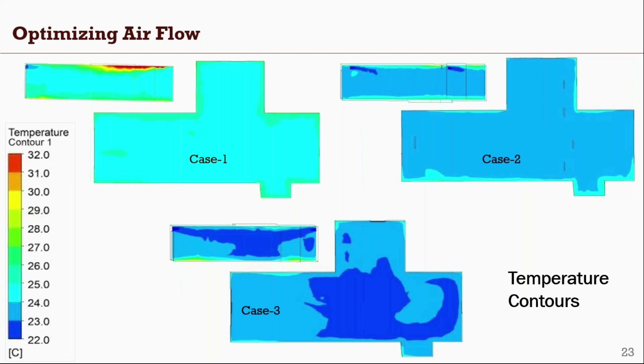This is the air velocity vector. In case 1, there are 4 diffusers from which velocity is flowing. In case 2, the diffuser location has been changed, and you can see the effect. In case 3, the diffuser location and number of diffusers have been changed. Case 3 has the lowest airflow speed at 1 meter height level, which is the standard height, and the occupant does not feel cold or any draft of cold air.